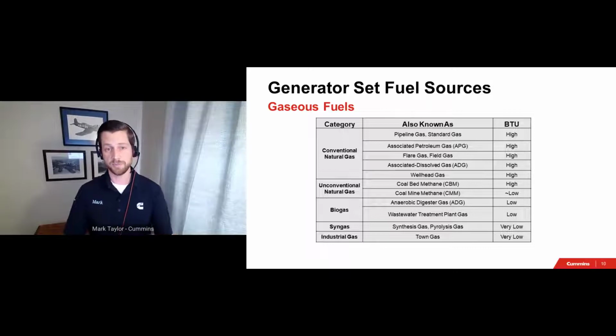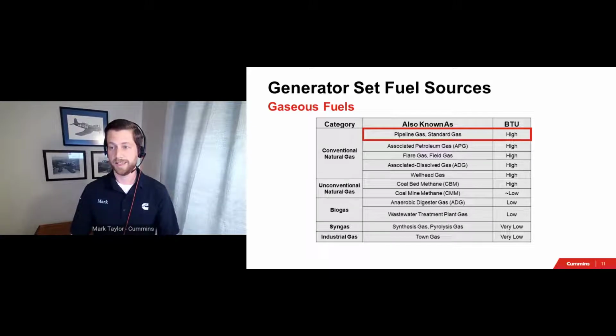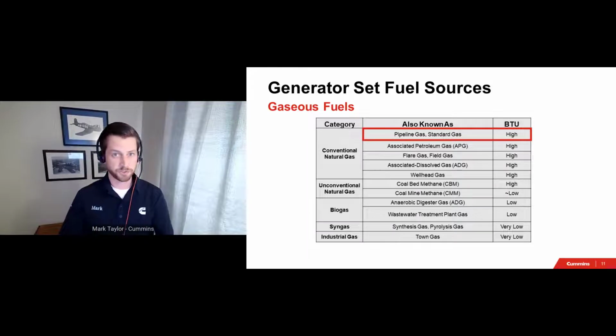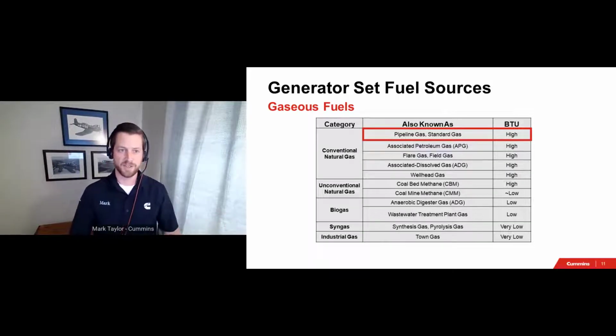This next table takes a deeper look at a variety of gaseous fuels, and you might even recognize a number here. But again, looking at energy content measured in BTUs this time, we'll start with pipeline natural gas on the high end of this list. Compared to other forms of fuel in the gaseous form, this will also very likely be the fuel used in standby applications. As you go down the list, many of these fuels may be a result of an industrial process or treatment. These fuels at times are consumed on site with a generator set designed for efficient continuous duty, or that fuel might be exported and cleaned and sold as a commodity.